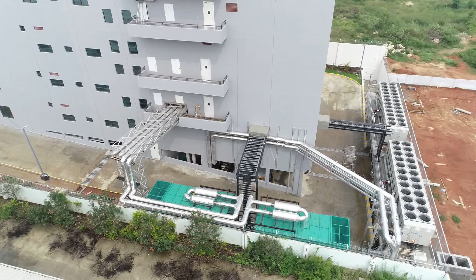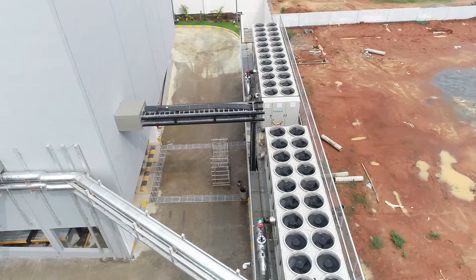Hi, this is Mahendra. I am GM Infra, Tele India. As rightly said, we have here also N+1 backup with our DGs, 2 numbers of DGs currently set up with 2 into 1010 kVA, and in future we have 2 more into 1010 kVA and 3 into 1500 kVA. And these are the two chillers presently we have with 430 TR into 2 numbers, and in future we have 2 into 150 TRs and another 2 into 400 TRs.